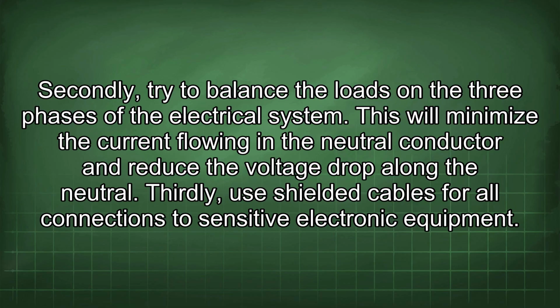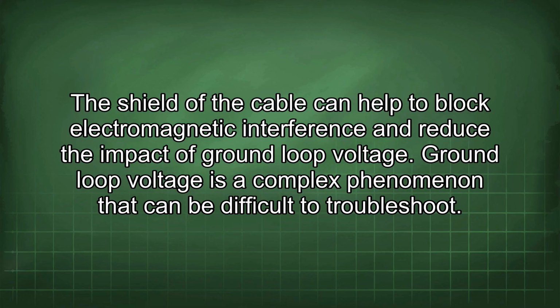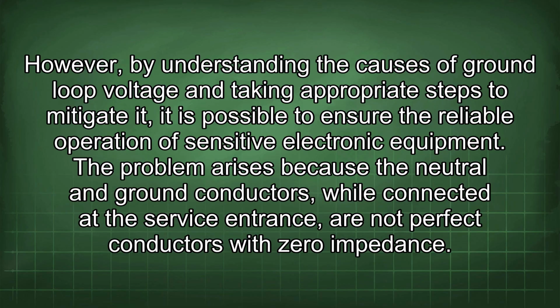Secondly, try to balance the loads on the three phases of the electrical system. This will minimize the current flowing in the neutral conductor and reduce the voltage drop along the neutral. Thirdly, use shielded cables for all connections to sensitive electronic equipment. The shield of the cable can help to block electromagnetic interference and reduce the impact of ground loop voltage. Ground loop voltage is a complex phenomenon that can be difficult to troubleshoot. However, by understanding the causes of ground loop voltage and taking appropriate steps to mitigate it, it is possible to ensure the reliable operation of sensitive electronic equipment.